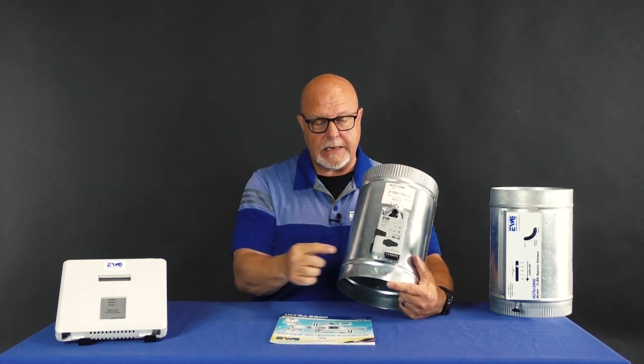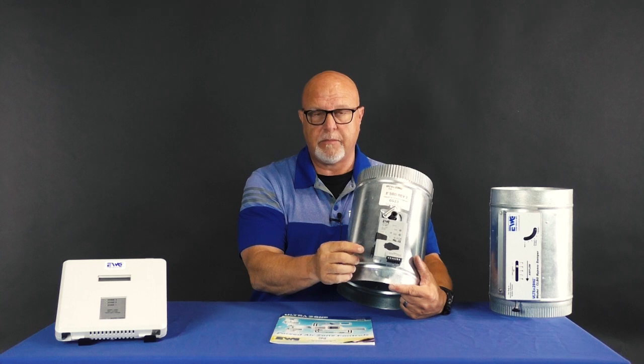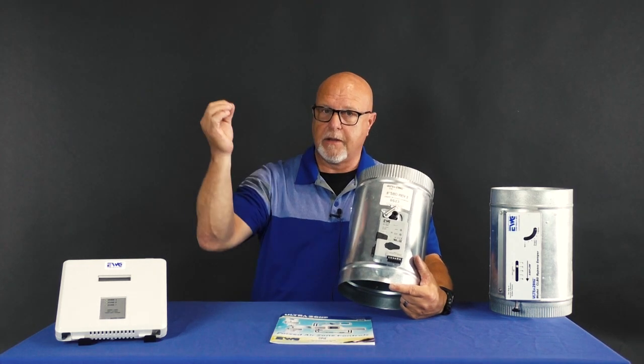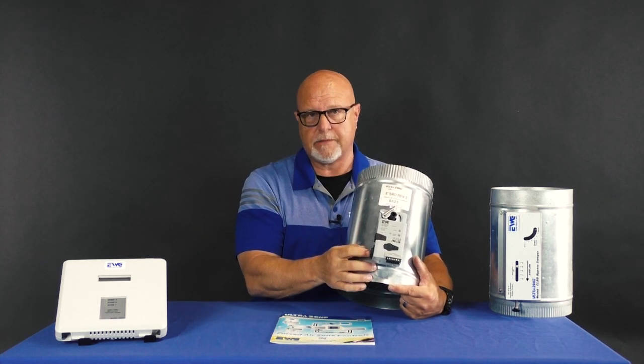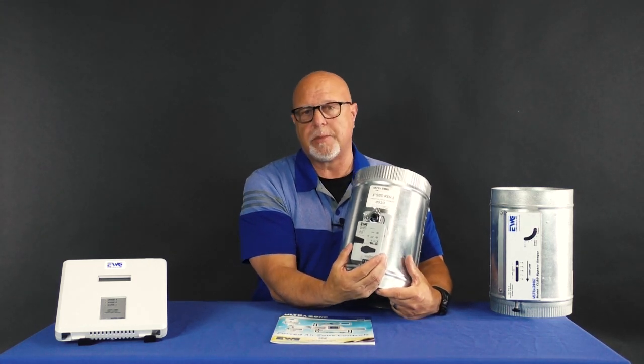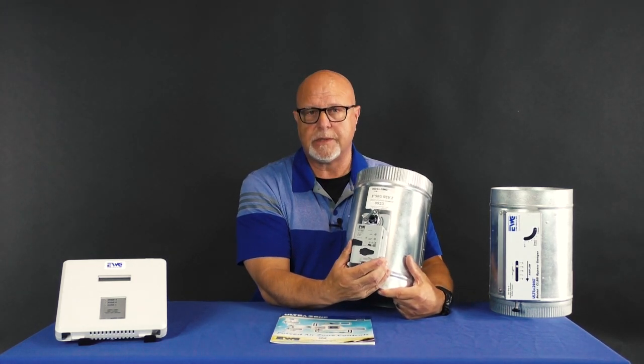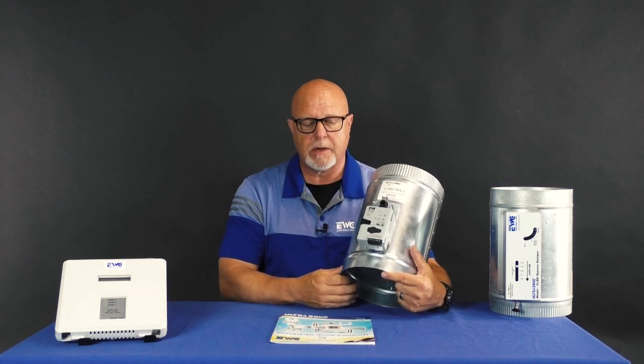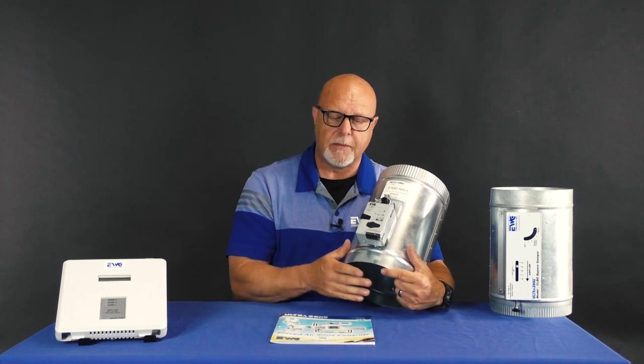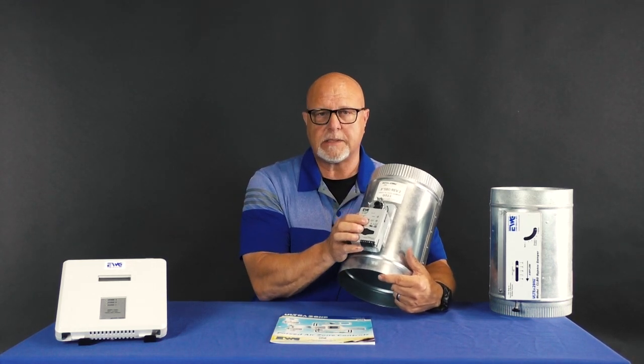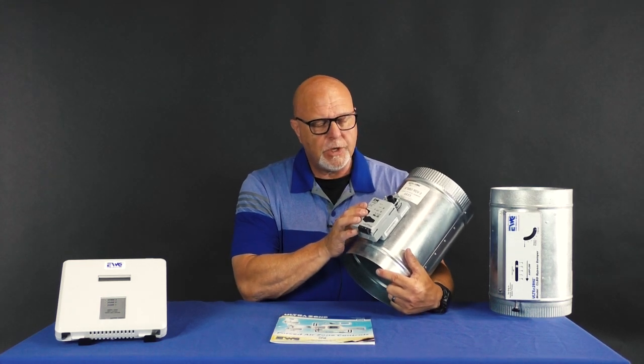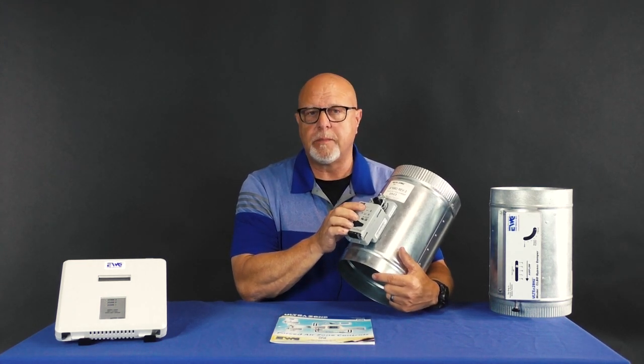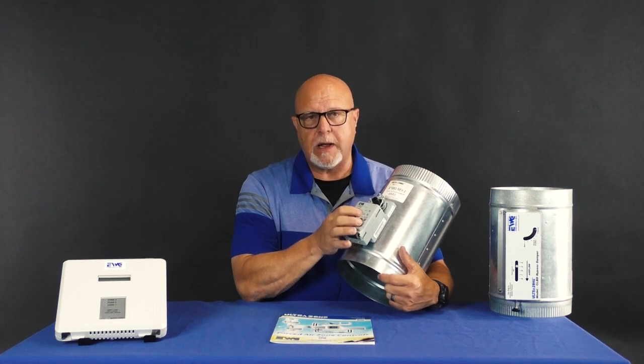From the supply into the positive side of the built-in sensor. From the return side to the negative side of the sensor. We have a built-in digital manometer that's made into this actuator. Once you have those installed and you have a dedicated 24-volt power supply to this damper, you will have a couple of lights that will be illuminated here. You will have a system light that will be green, and you will have a blinking yellow light. The blinking yellow light is the bypass setup button.